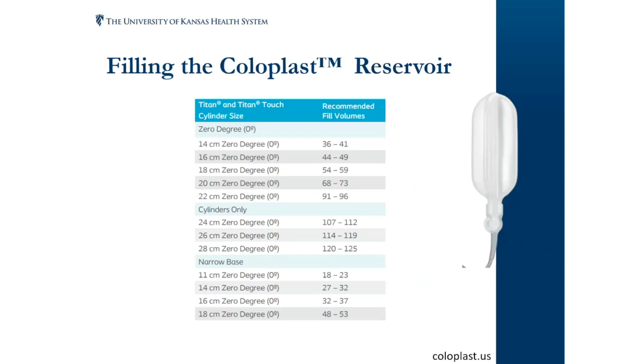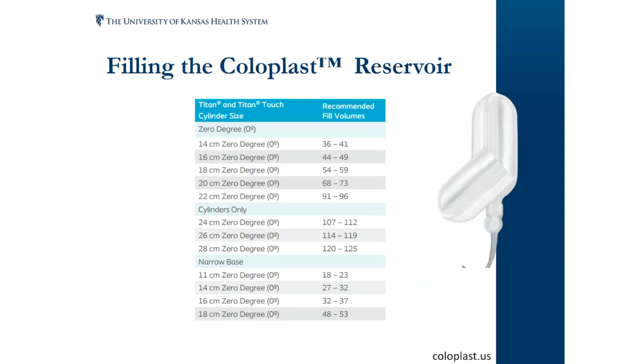But there is something important. If you're going to use the 125 reservoir and underfill it, you need to make sure you fill it enough. What I have demonstrated here with this really poorly designed animation is the Pac-Man effect, as it's so called. It's when the device is filled so little that the actual fluid ends up in the head of this Pac-Man and the neck is folded over because it's underfilled. And when you go to exchange fluid, there's no way to create that vacuum effect and pull that fluid in, rendering the device malfunctioning and potentially needing revision. I want you to remember that number, 80 milliliters, because it's going to come up again. So do not fill this less than 80.